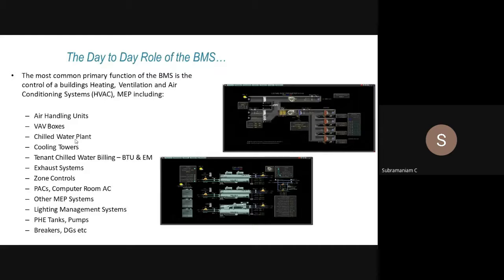So how will the BMS do it? Whatever you do mentally, you have to sequence it. You have to write it in a program, a flowchart kind of thing. All that you have to transfer into control logic. First I will do this, second I will do this, third I will do this. When we do all that, that is BMS. That is what we are doing for the air handling unit and VAV box. It will do the same for the chiller plant, cooling tower, and tenant chilled water.